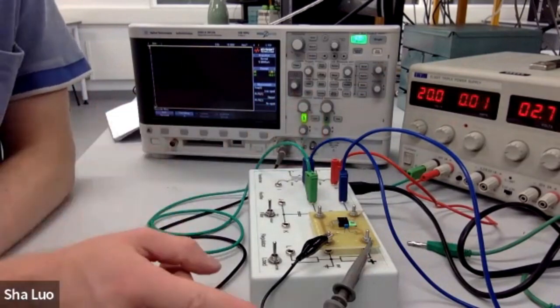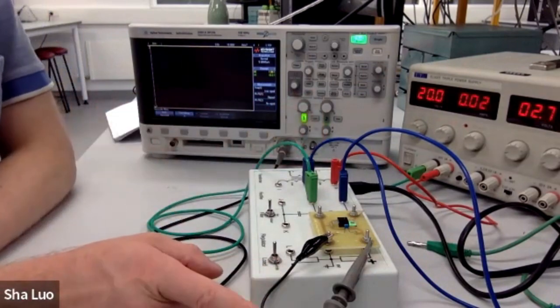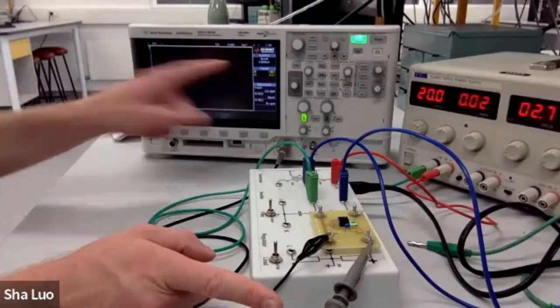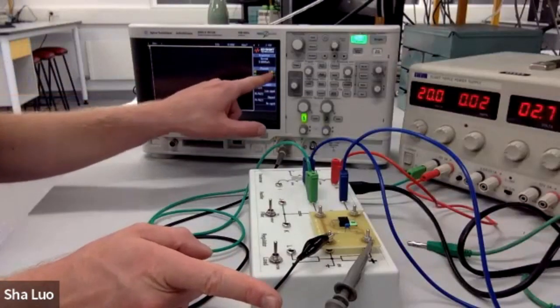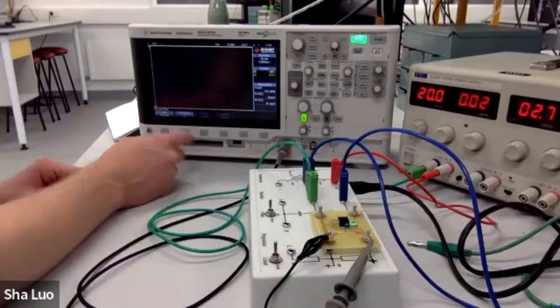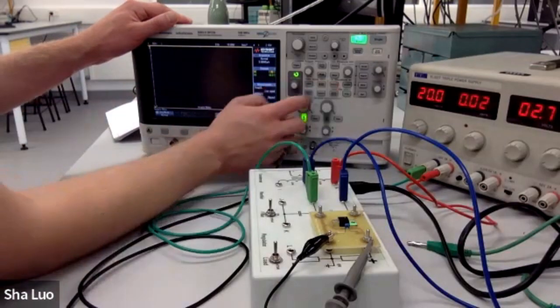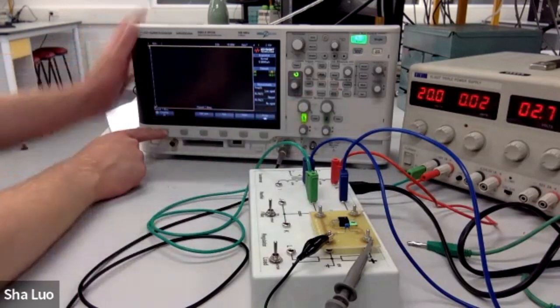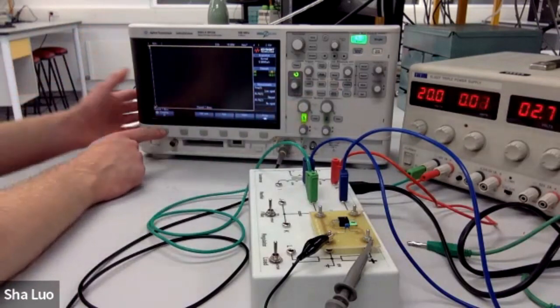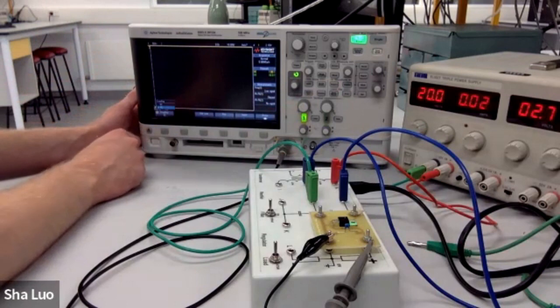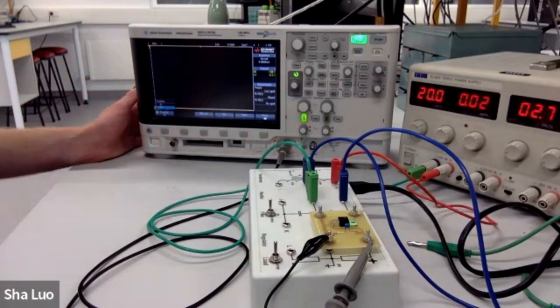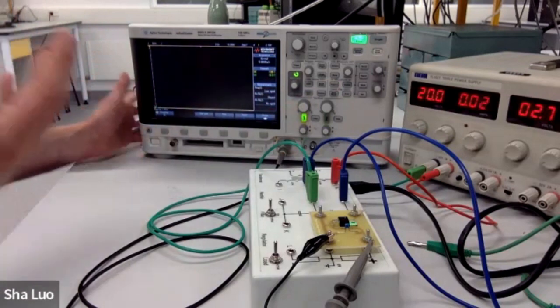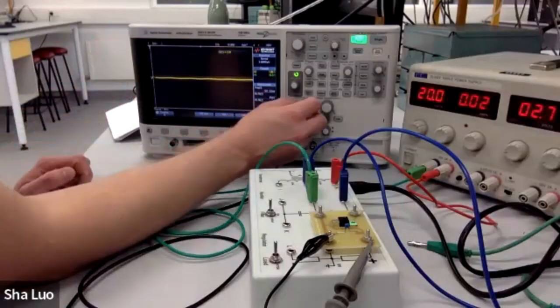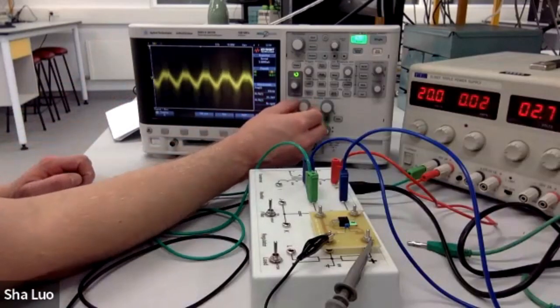What I'd like to do to get around this is, first of all, have the oscilloscope probe set to 1 times rather than 10 times. That gives a bit more precision. I've also set the oscilloscope to be on 1 time as well. And I can change what's called the coupling of this channel. So I go to channel 1, currently it's in DC coupling, that basically means measure everything. I can change it to AC coupling, which says basically ignore all the DC component, just show me the AC component. If I bring that back on screen, I can now dial that up.